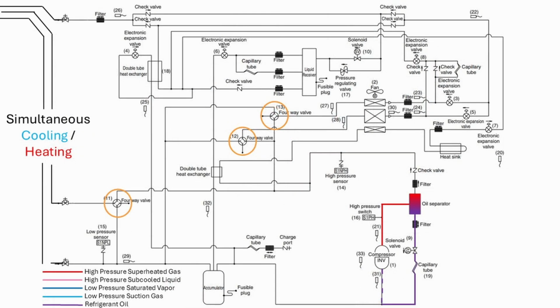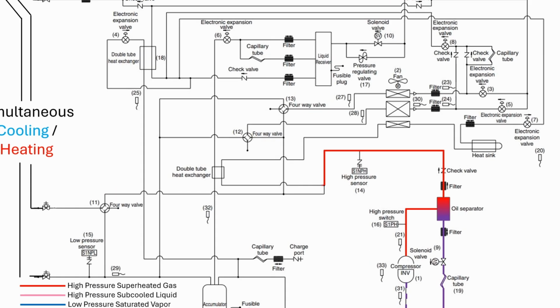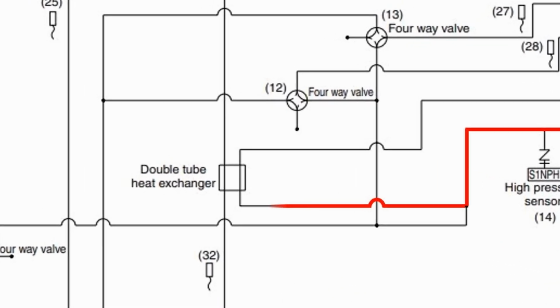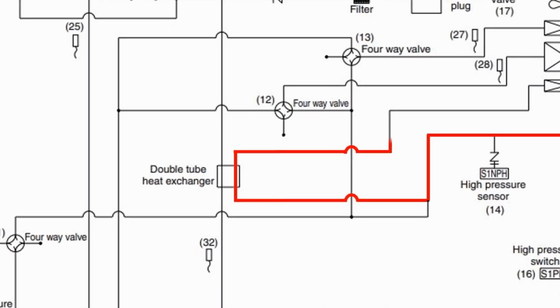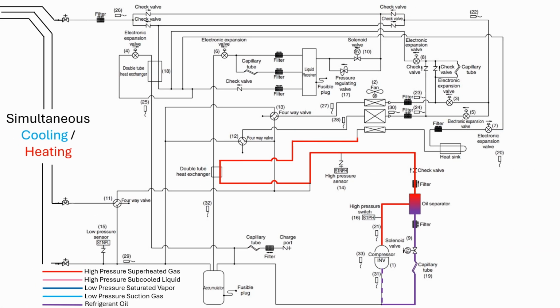Also notice that the outdoor unit is equipped with 3 four-way valves. These valves are used to control the flow of refrigerant through the system to not only control the mode of operation, but also direct refrigerant to the correct sections of outdoor coil to accurately superheat or subcool. The refrigerant leaves the oil separator and passes through a filter or strainer on its way to the tube-in-tube heat exchanger, and then on to the smallest section of outdoor heat exchanger.